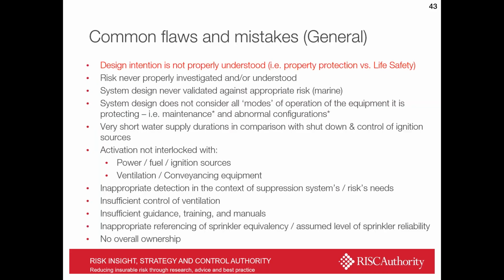Now, based on some of the things that we've seen when we've been doing forensic examination of failures of all types of suppression systems, not just Watermist, the first and key one is that design intention is not properly understood. Be it whether it's to do with property protection or life safety, we do see things more fundamental than that: an assumption that the system would extinguish the fire, but actually it didn't, and it wasn't associated with an alarm system. So not only did it not extinguish the fire, it also didn't raise an alarm that there was a fire, and then the building carries on to burn down anyway. These are quite fundamental issues. The risk never properly investigated or understood properly. We see an inappropriate use of systems applied to different applications.